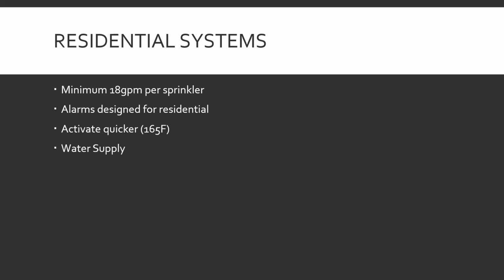There could be on-site pressure tanks, like in rural areas. That's like a big tank on the hill full of water, and when the system goes off, pressure in the tank feeds the system, or a storage tank with a pump. That could be pretty much what it sounds like. Instead of being a straight tank, there could be a little pump to help boost pressure. Both of these last ones are based on calculations for the size of your tank. I need a tank that can hold, blah, blah, blah gallons of water because my house is this big with this many sprinklers and that kind of thing.